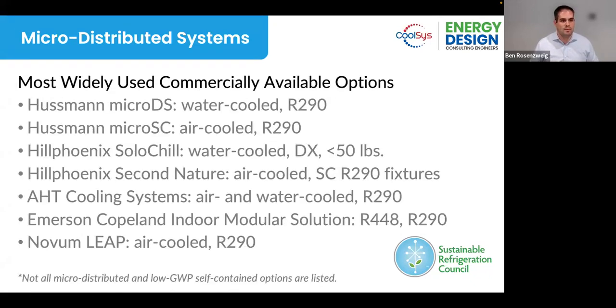Next slide, please. So the most widely used commercially available options here, and not all are listed, are things like the Hussmann Micro DS and Micro SC options, which are air and water cooled propane, the Hill Phoenix Solo Chill and Second Nature options, which are DX as well as self-contained using either R448 or propane, AHT cooling systems, air and water cooled units that use R290. Emerson's Copeland Indoor Modular Solution, which uses R448 and R290, and Novum Leap self-contained equipment using R290.